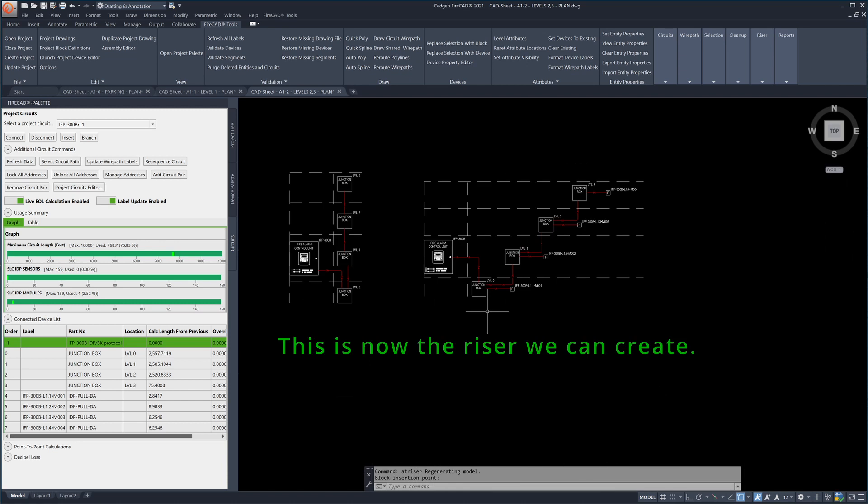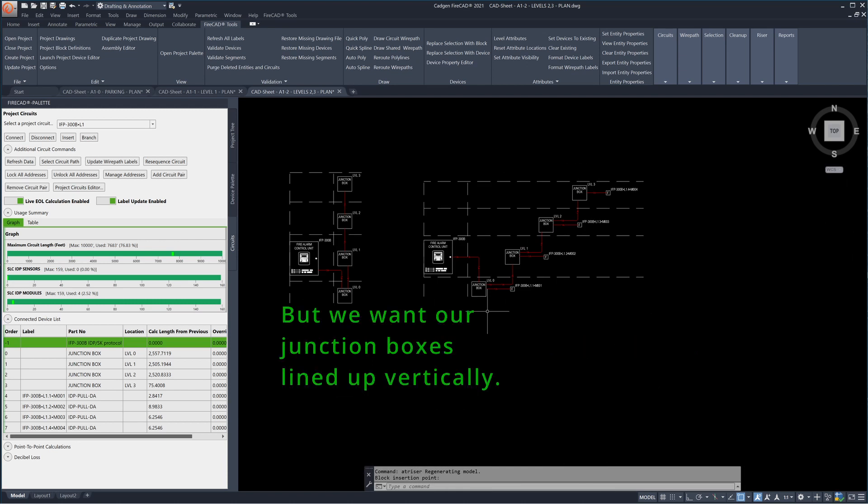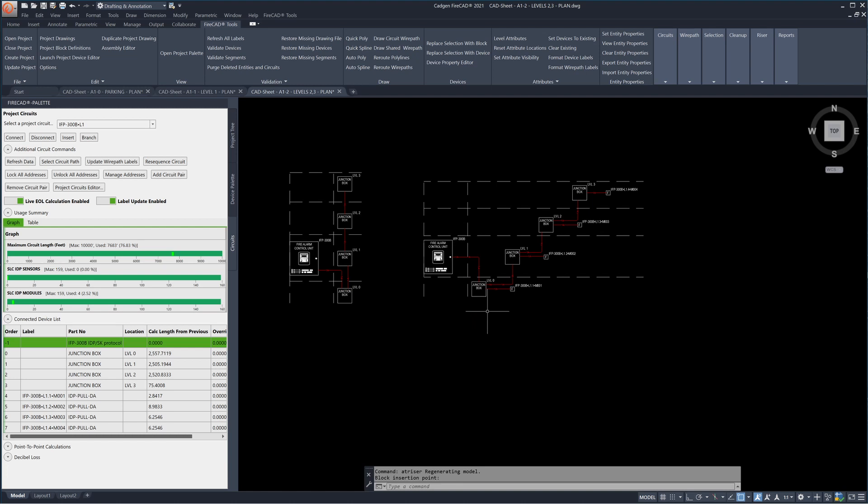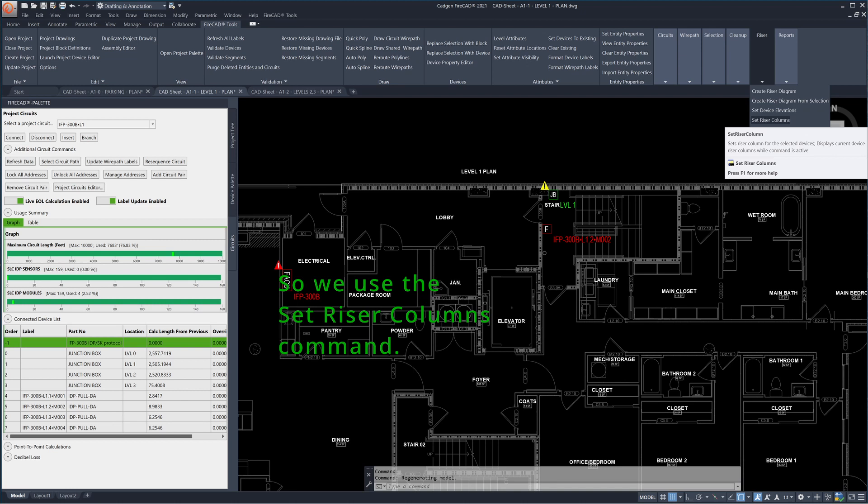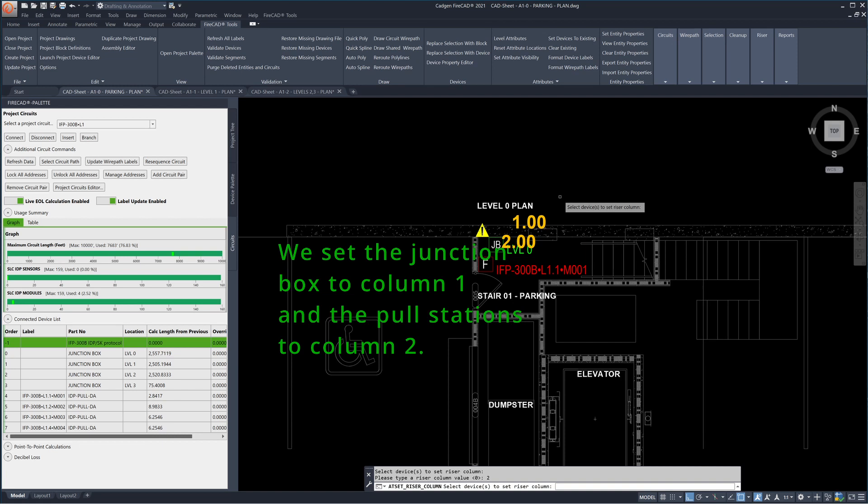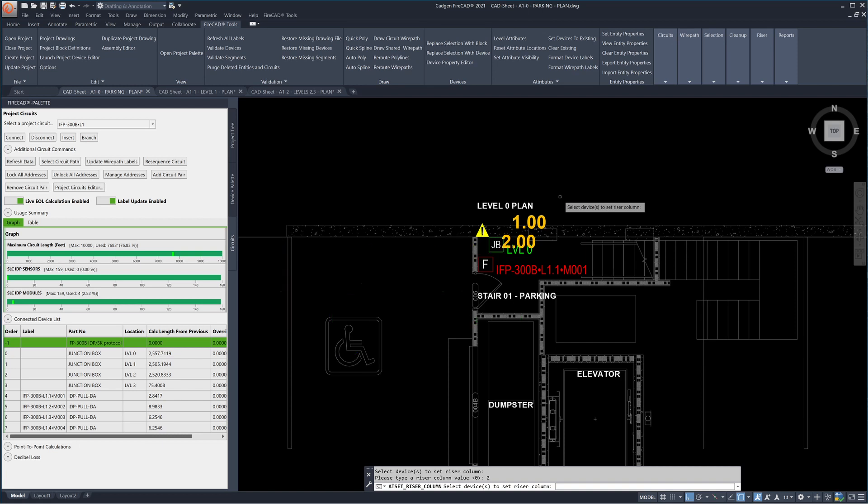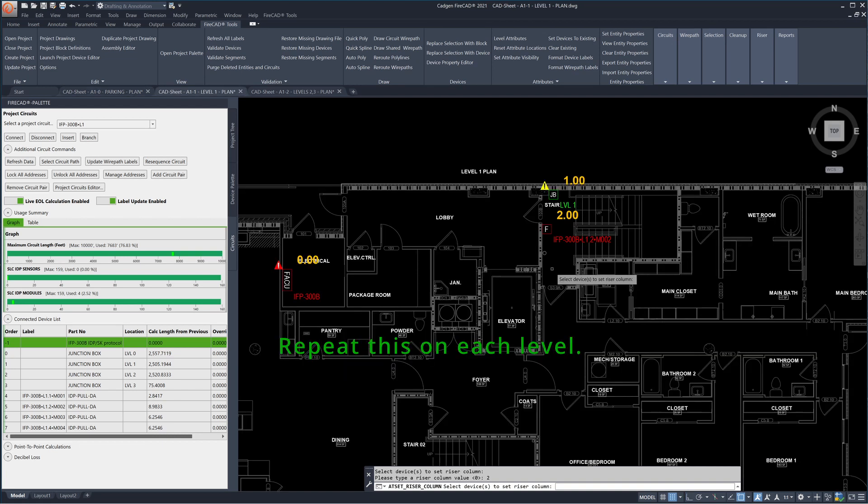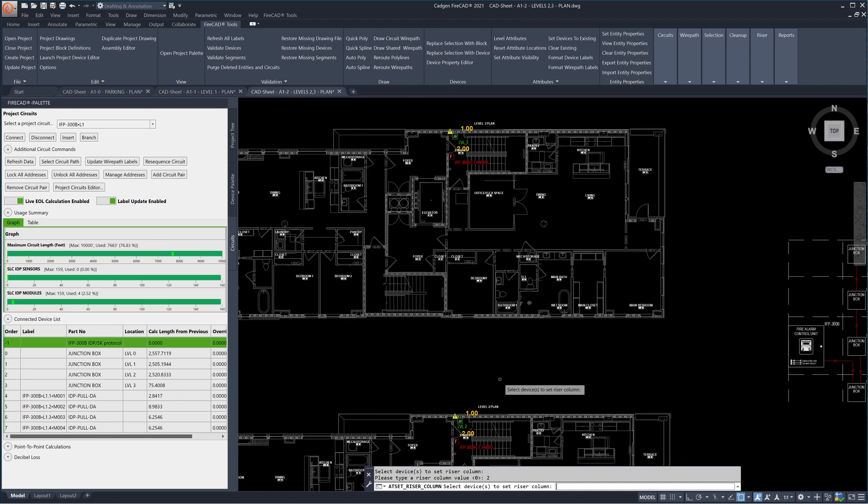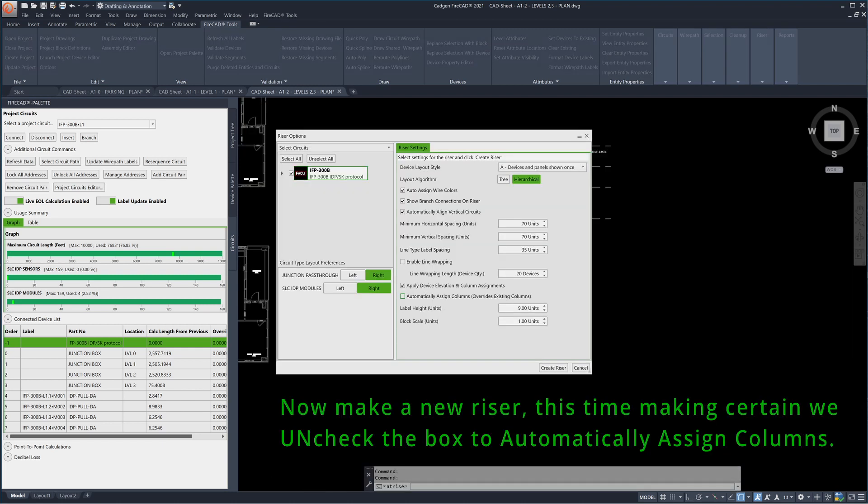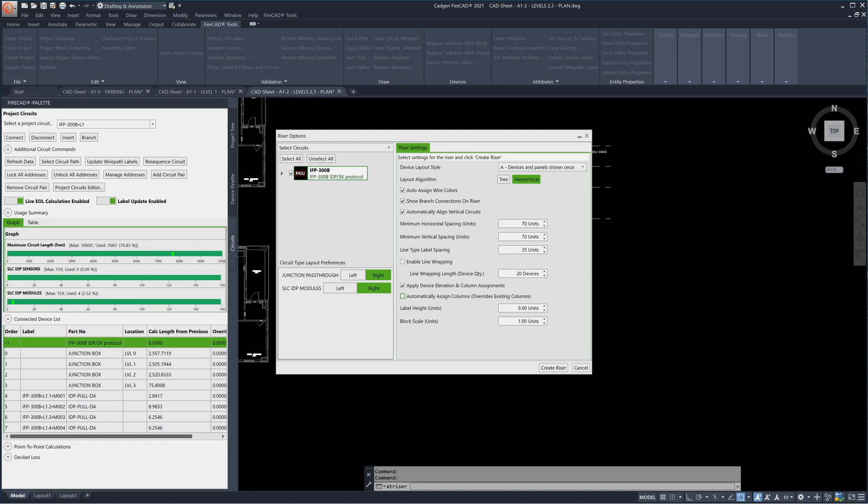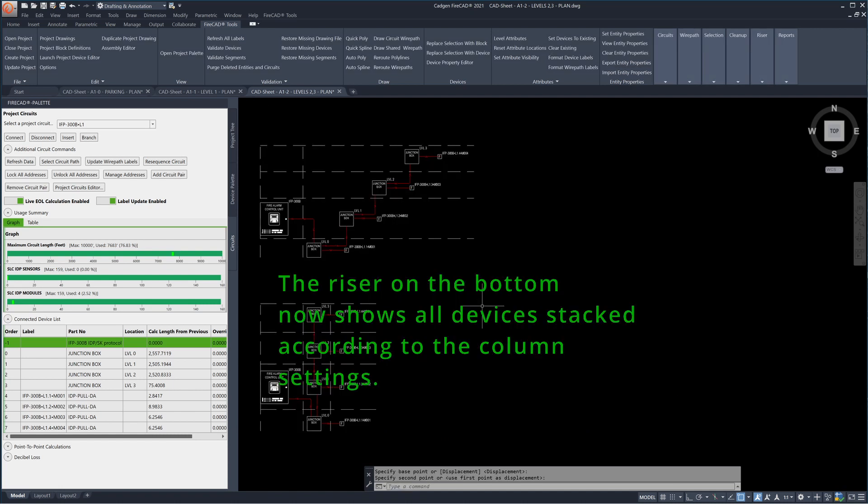This is now the riser we can create. But we want our junction boxes lined up vertically. So we use the set riser columns command. We set the junction box to column 1 and the pull stations to column 2. Repeat this on each level. Now make a new riser, this time making certain we unchecked the box to automatically assign columns. The riser on the bottom now shows all devices stacked according to the column settings.